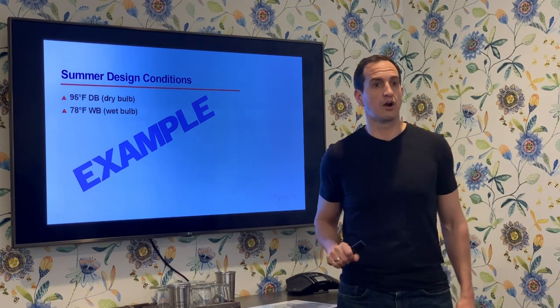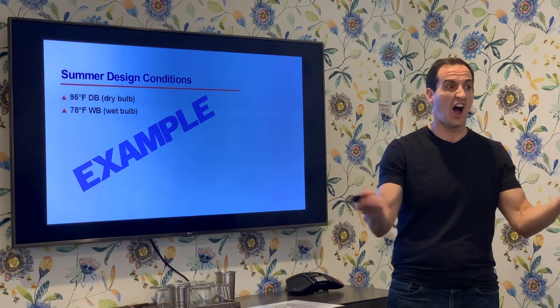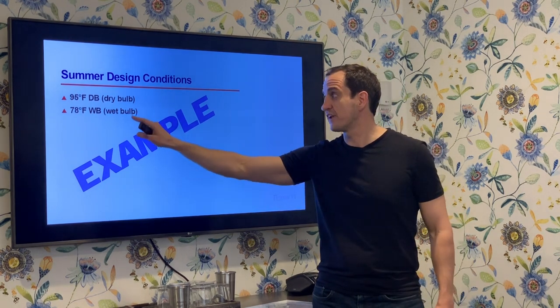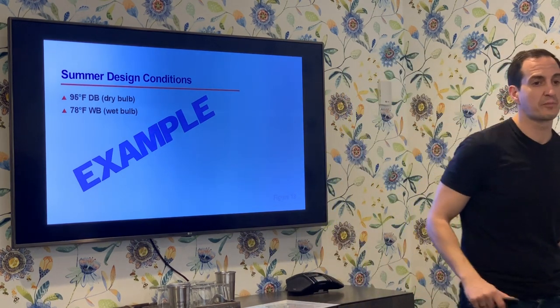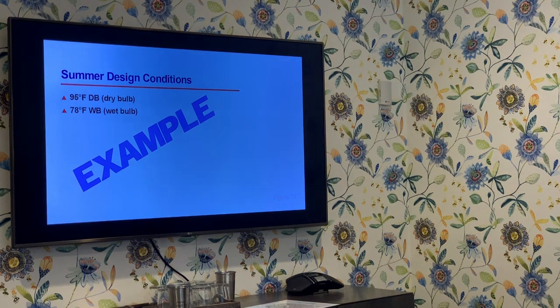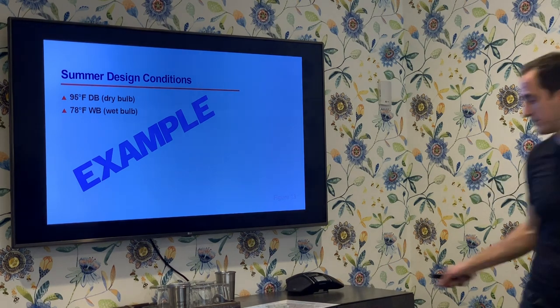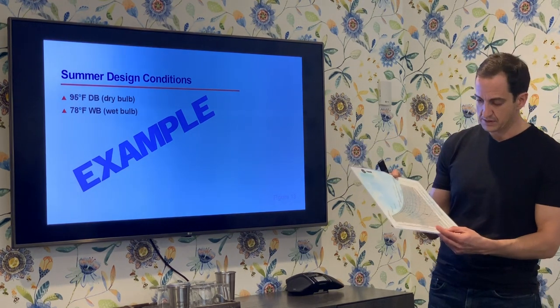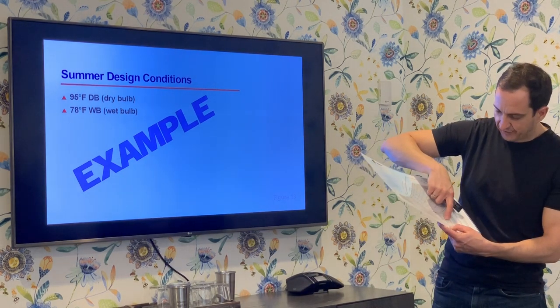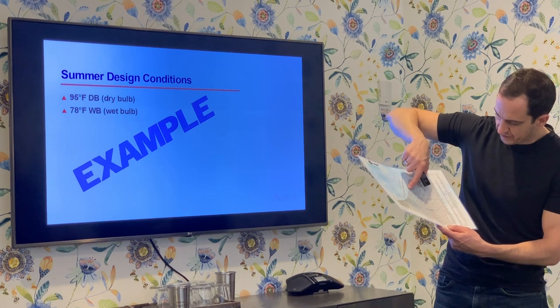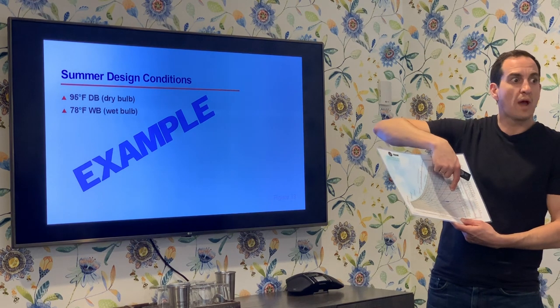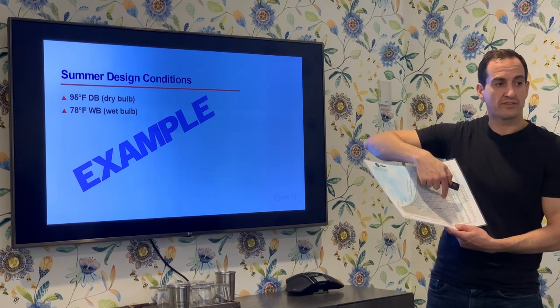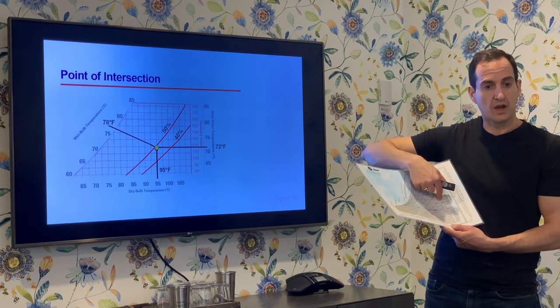Let's say we've got our dry bulb and wet bulb thermometers and we go outside on a hot, humid day in Atlanta. We measure 95°F dry bulb and 78°F wet bulb. Take a moment to look at your psychrometric charts. On the x-axis find 95°F between 90 and 100, then look at the wet bulb lines and take the 95°F line up until it crosses the 78°F wet bulb line. Put a dot there — that's where we are.